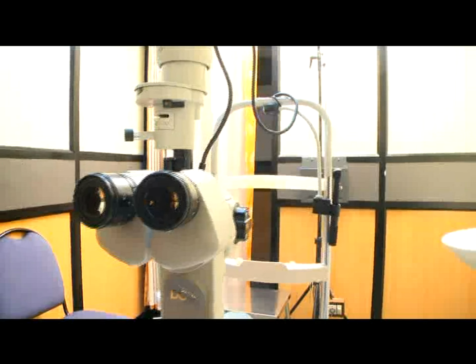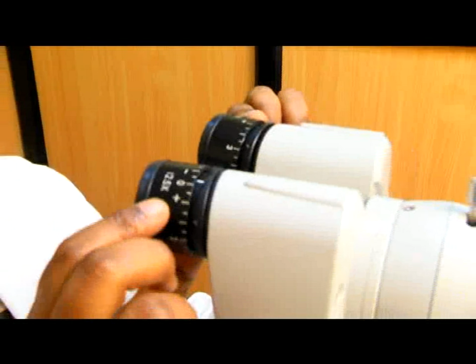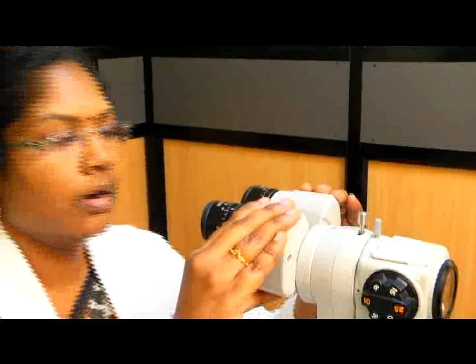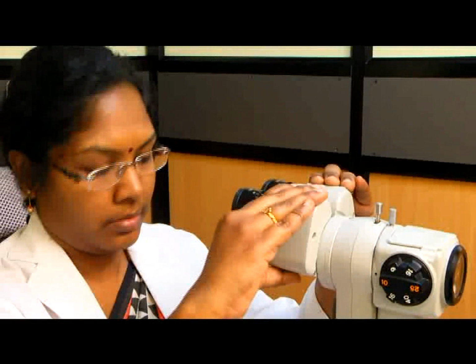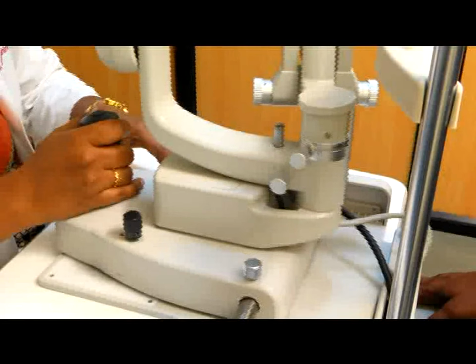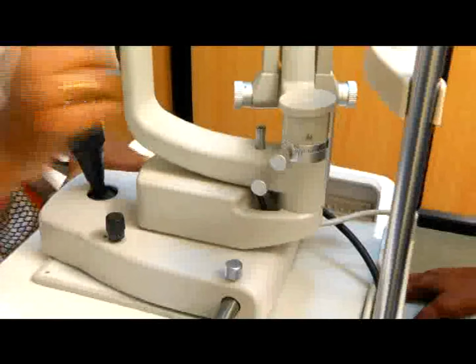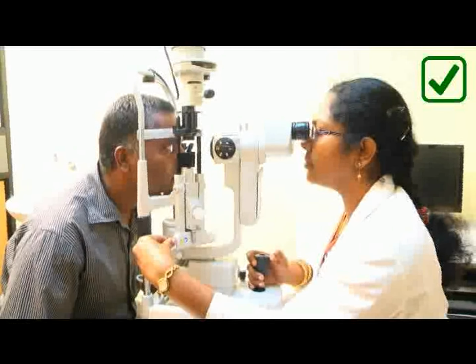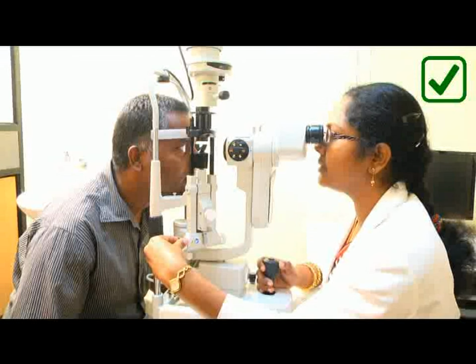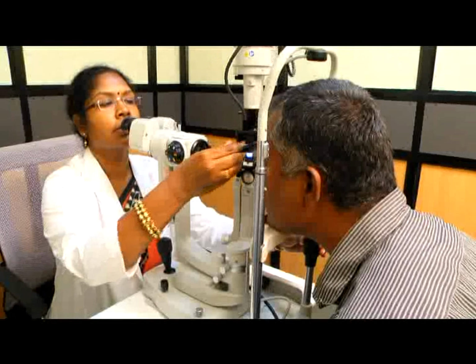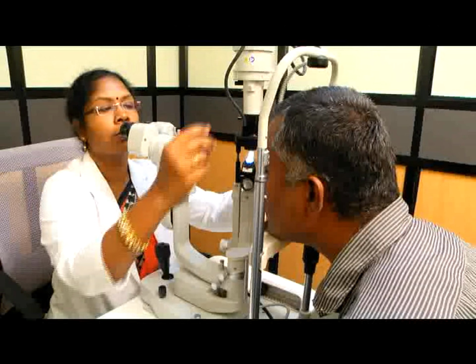Before starting to use the slit lamp, adjust the focus of the eyepiece to 0, adjust the interpupillary distance, and lock the slit lamp, and check that the slit lamp is parallel on the table. Make sure that the observer and the patient are seated comfortably.